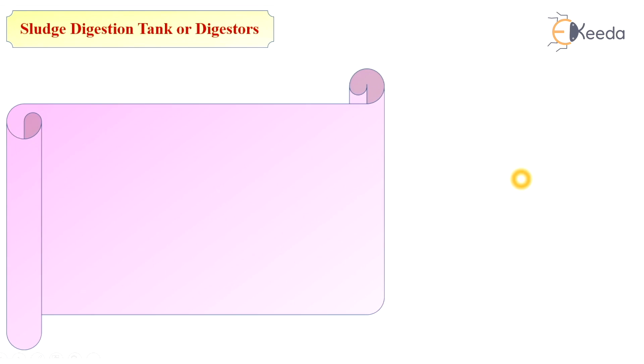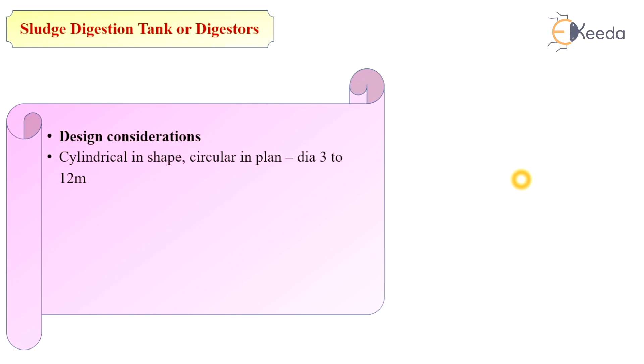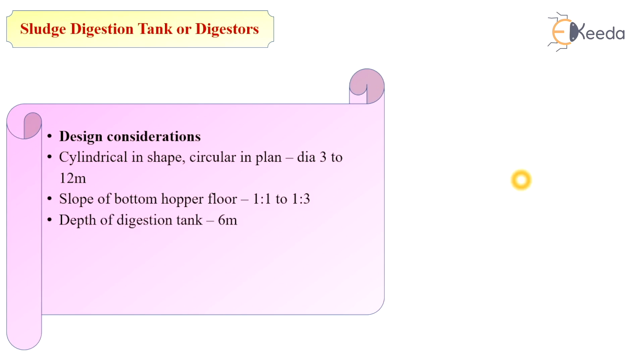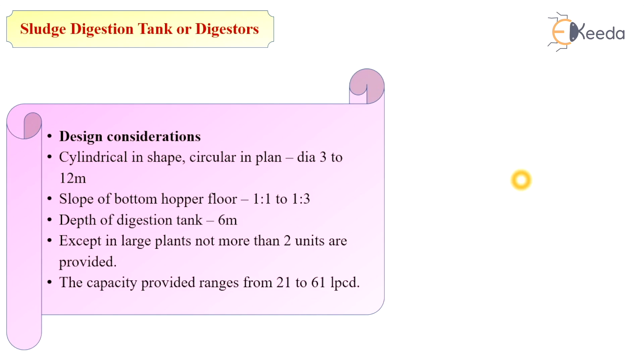Before starting the actual design, we need to know some design parameters and criteria. The digestion tank is cylindrical in shape and circular in plan, with an approximate diameter of 3 to 12 meters. The slope of the bottom hopper floor is 1:1 to 1:3. The depth of the digestion tank is 6 meters. Except in large plants, not more than 2 units are provided. The capacity provided ranges from 21 to 61 liters per capita per day.